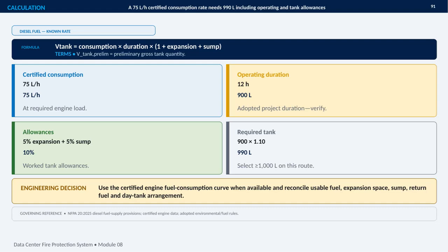This slide shows the diesel fuel tank calculation using a known, certified consumption rate. The engine consumes 75 liters per hour at the required load, and the adopted operating duration is 12 hours. That gives us a basic operating volume of 900 liters. We then apply the listed tank allowances, 5% for fuel expansion and 5% for the sump, for a combined allowance of 10%. Using the formula, preliminary tank volume equals consumption multiplied by duration, multiplied by 1 plus the expansion and sump allowances. In this case, 900 liters times 1.10 produces a required tank volume of 990 liters.